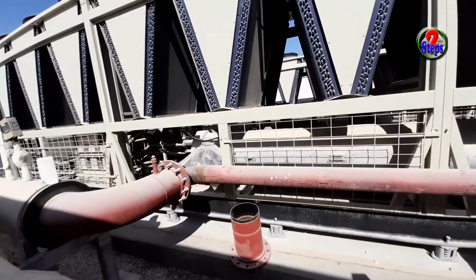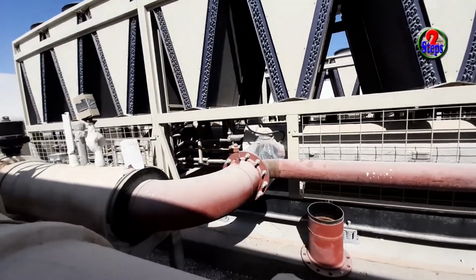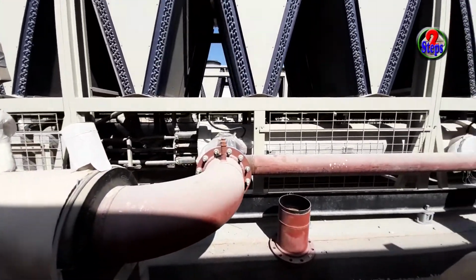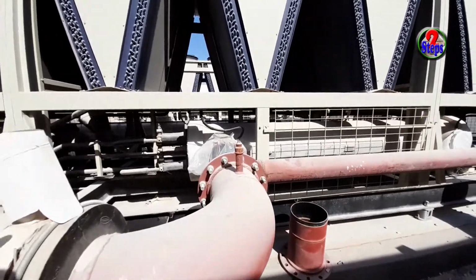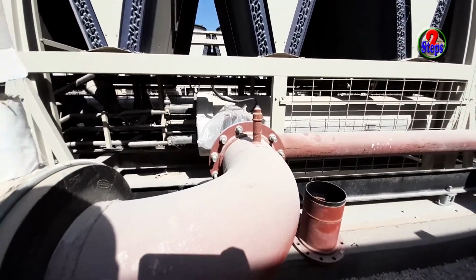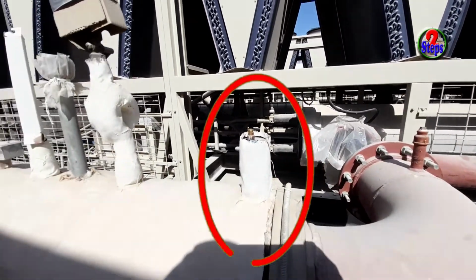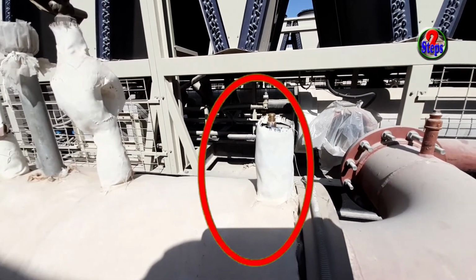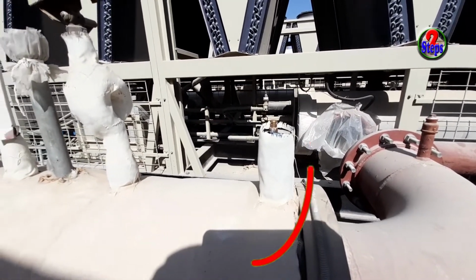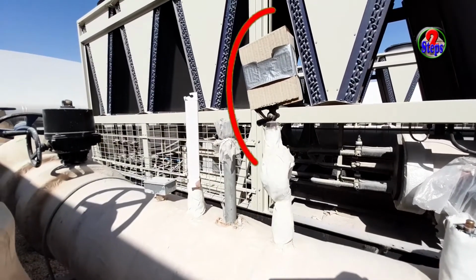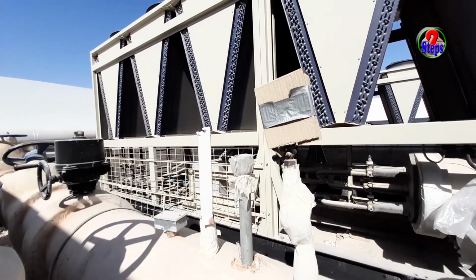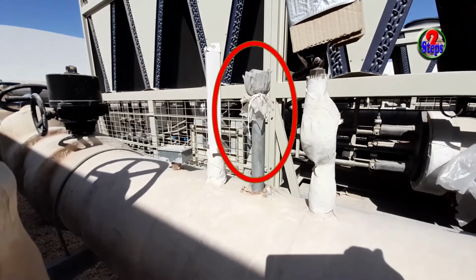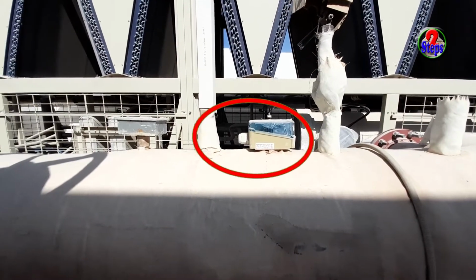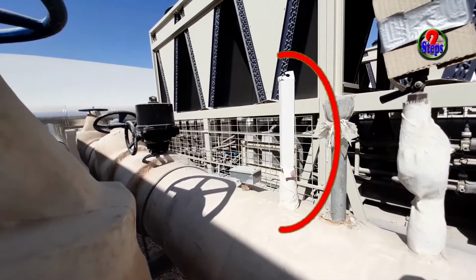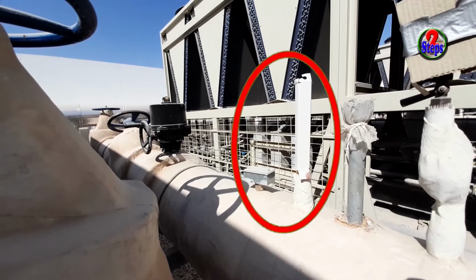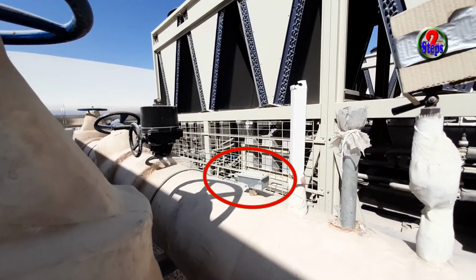Here we make a temporary bypass for the inlet and outlet connection for the flushing. That's why we remove the connection from the unit, for unit safety. This is the automatic air vent. After that, this is the pressure gauge. Here is one point for flow switch. After that, this one temperature sensor. Then this is the thermostat point.